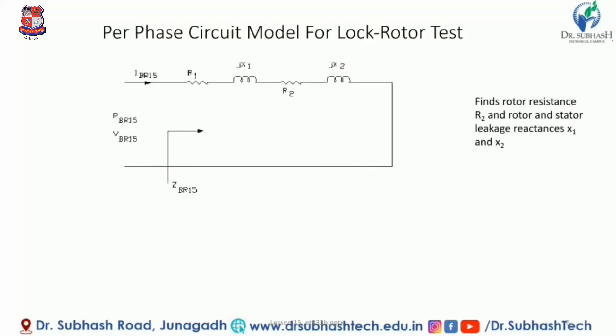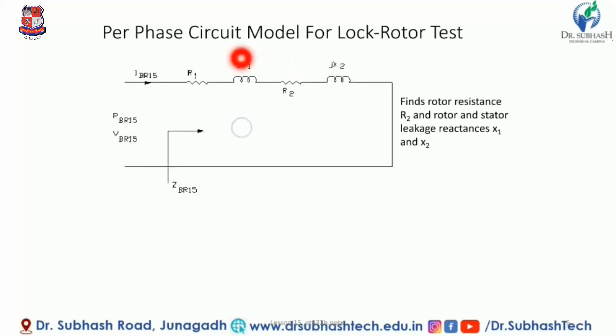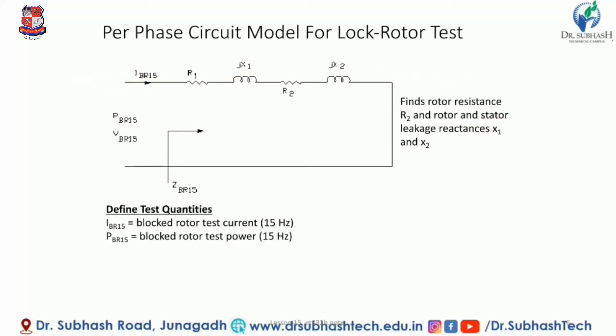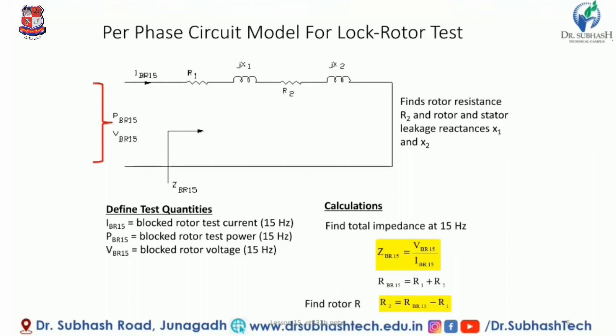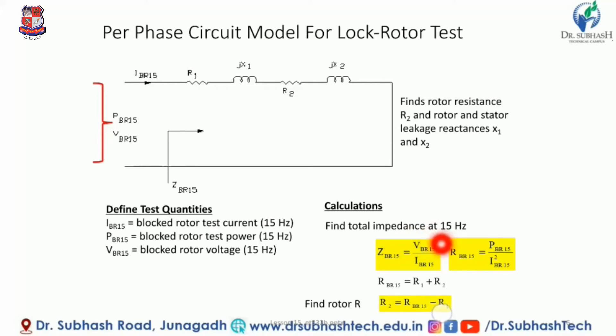Using the per-phase circuit model for the Lock Rotor Test, we find the rotor resistance R2 and rotor and stator leakage reactances jX1 and jX2. Define the test quantities: V_BR15 is the block rotor test voltage at 15 Hz, I_BR15 is the block rotor test current at 15 Hz, and P_BR15 is the block rotor test power. The total impedance is: Z_BR15 = V_BR15 / I_BR15.